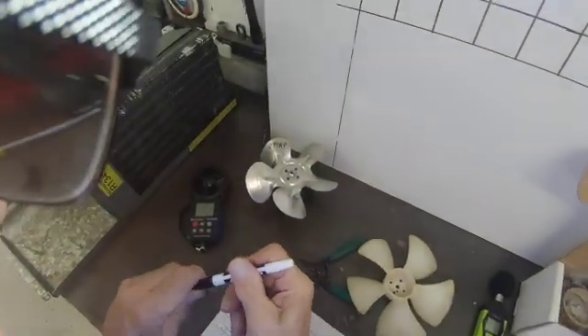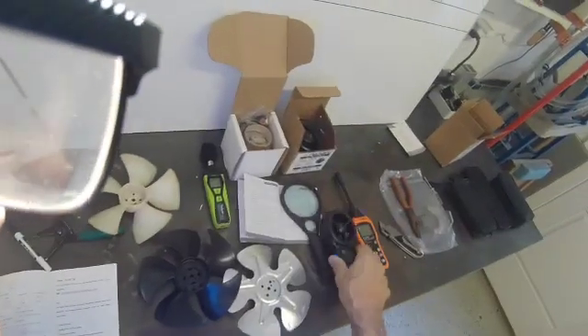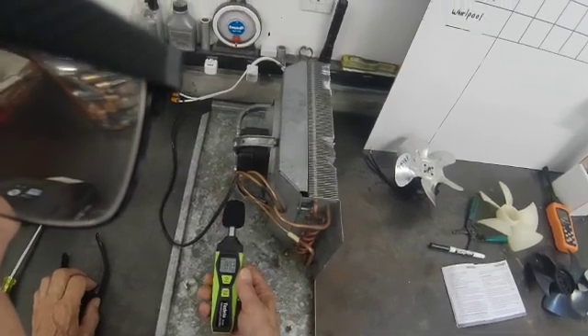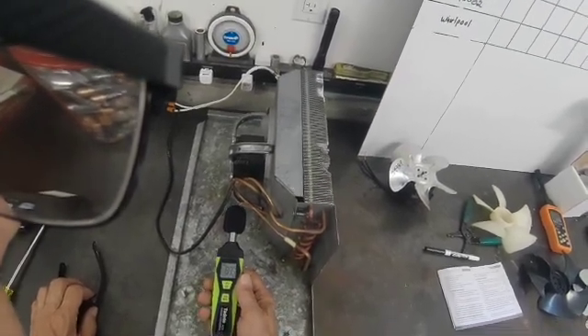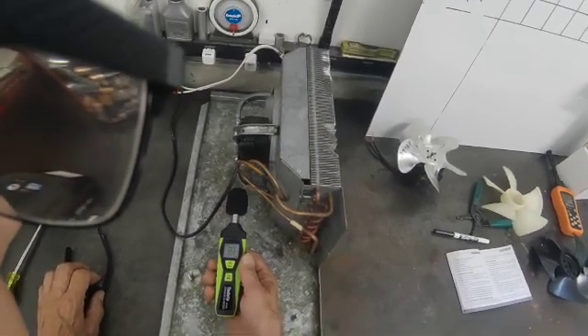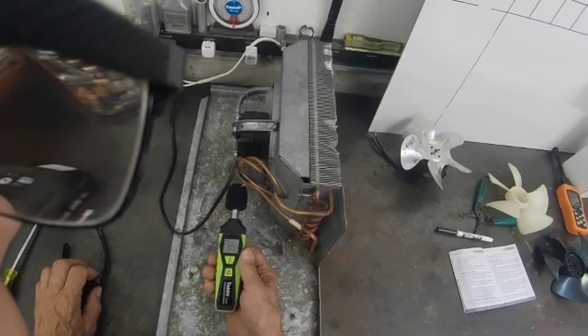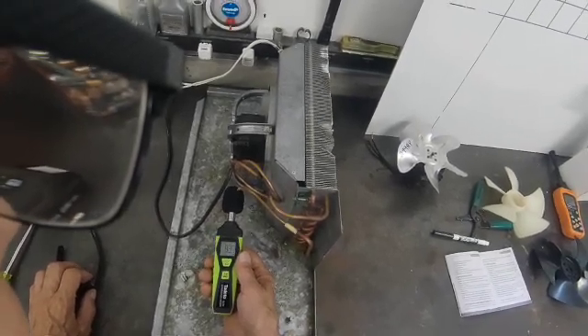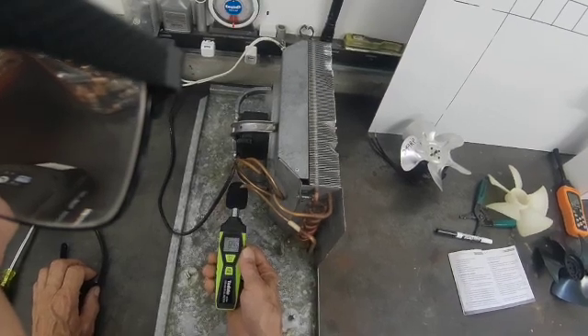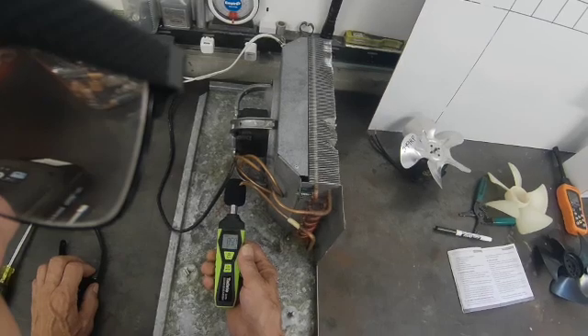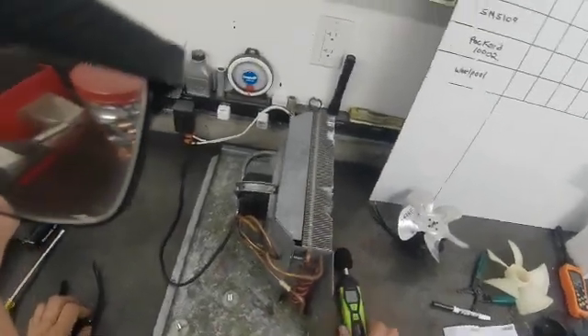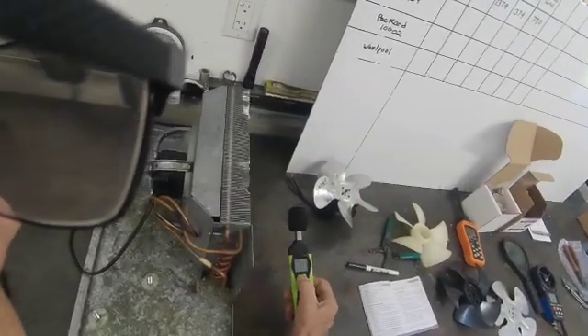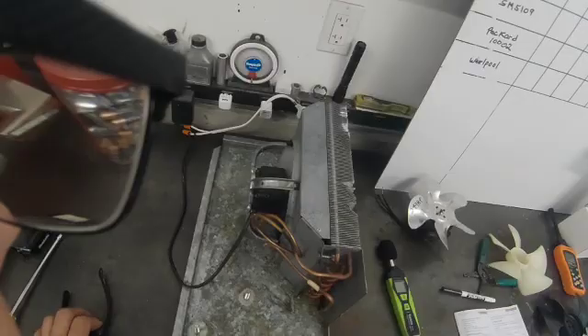Okay, the next thing we'll measure is the noise level. We're testing this from the rear because this is where the noise is coming from, it's not in front of the condenser, but behind it. And we're getting a value of, it's fluctuating between 84, 85. All right, let's say 85 on average. I will change this and change the blade and see what kind of a difference we get.